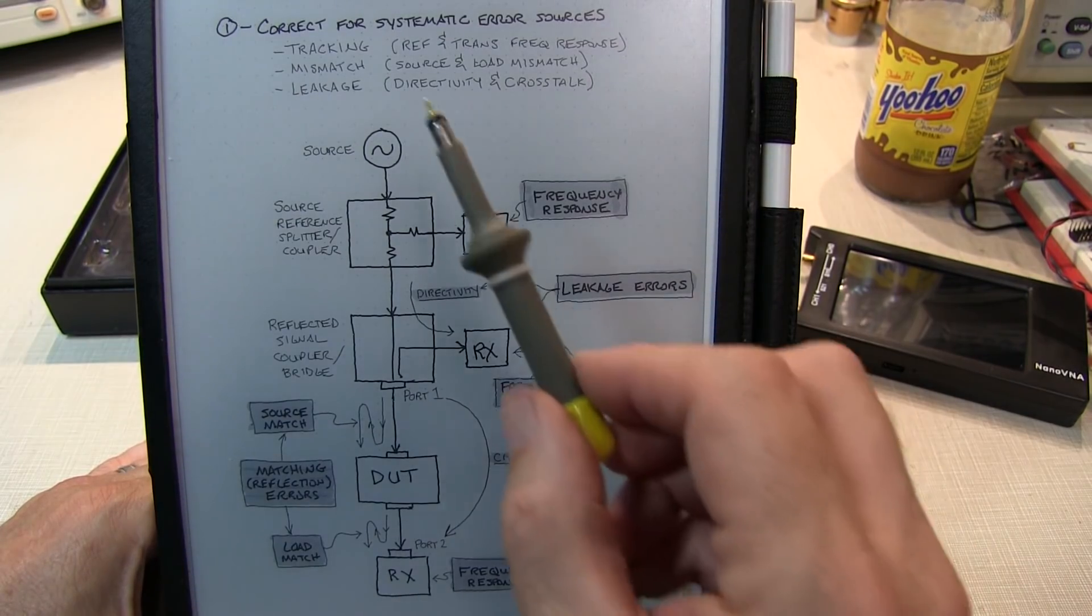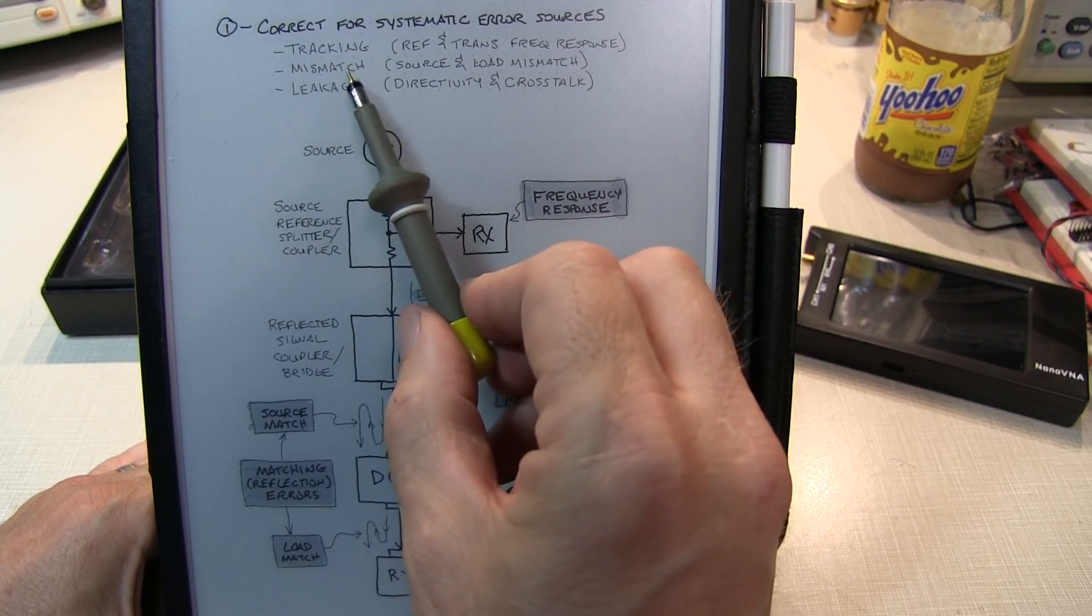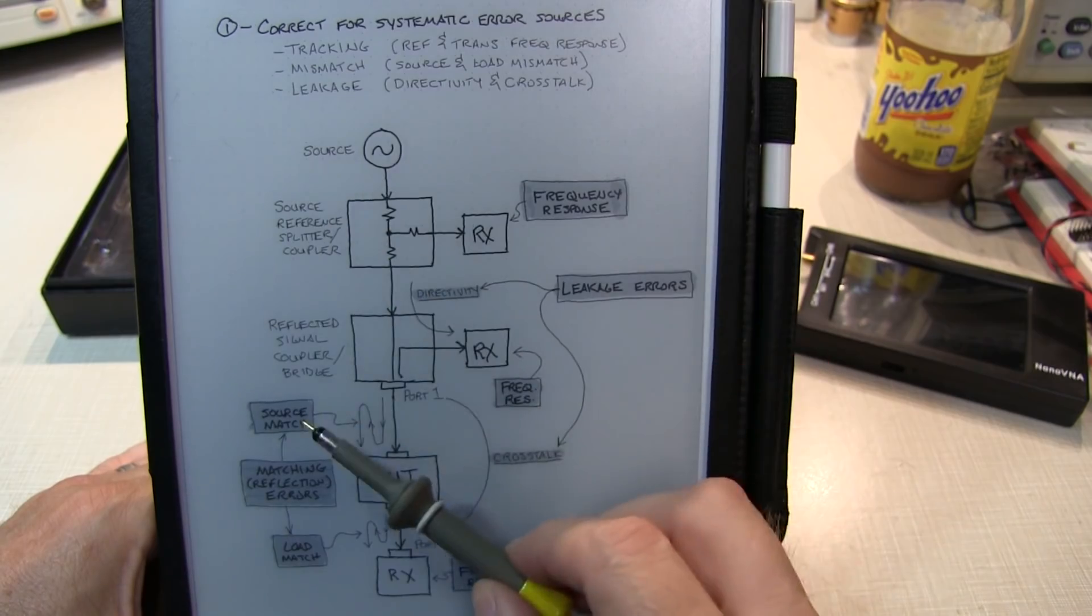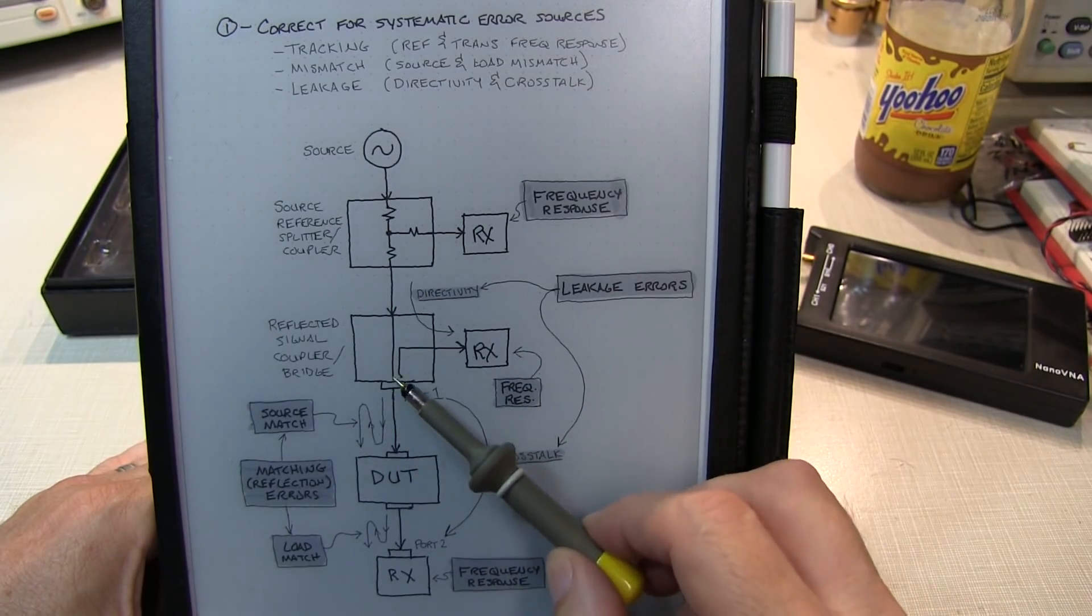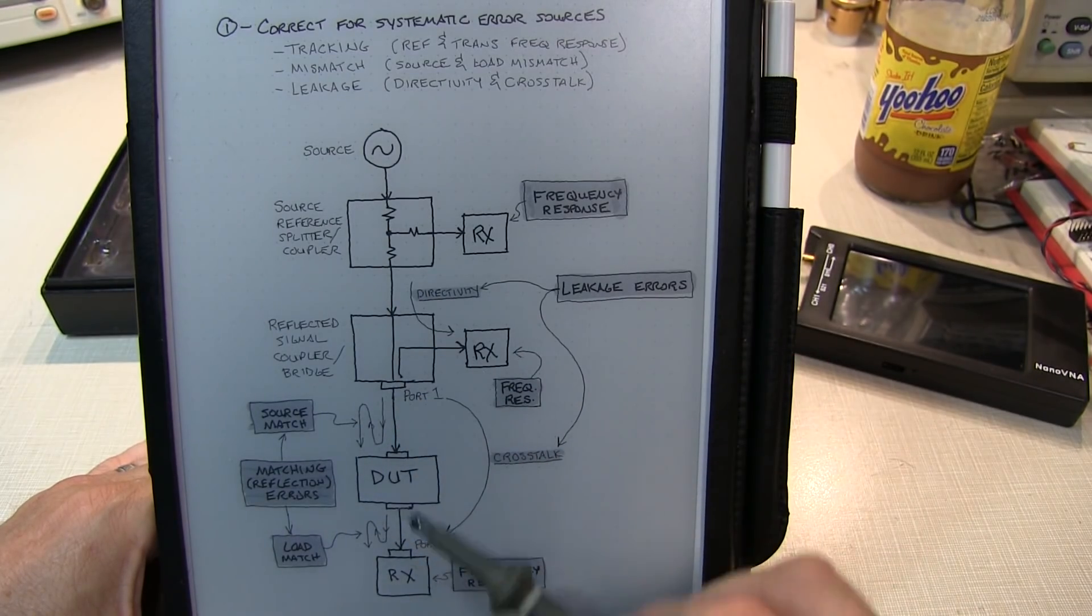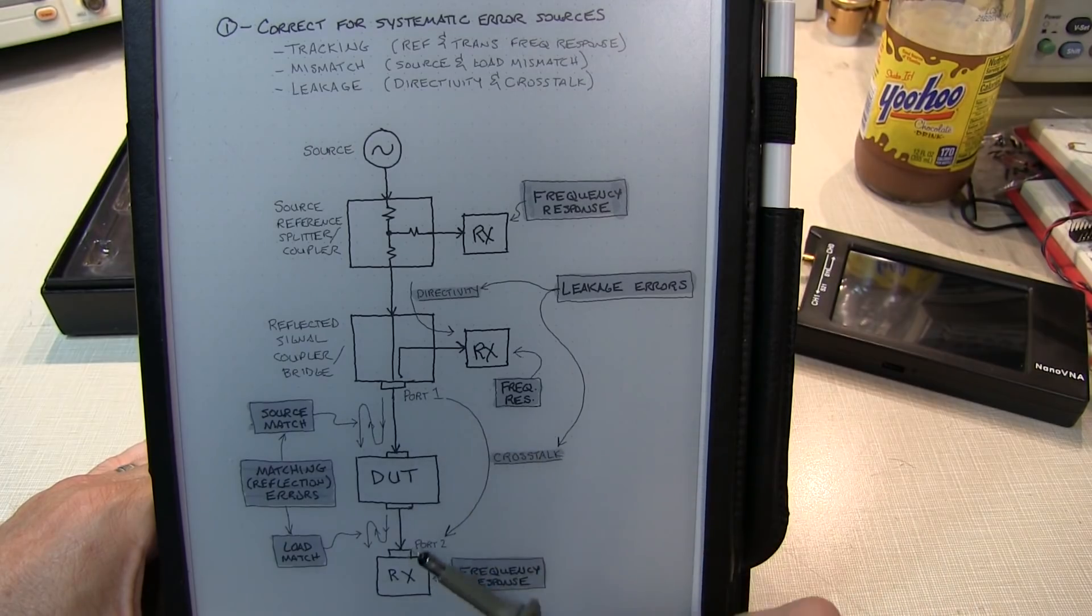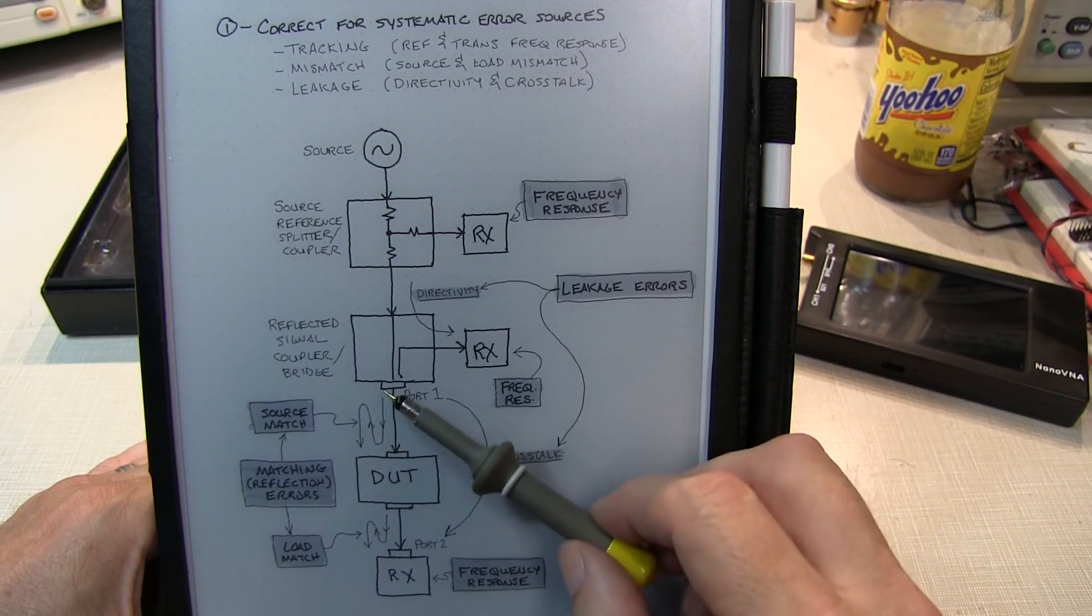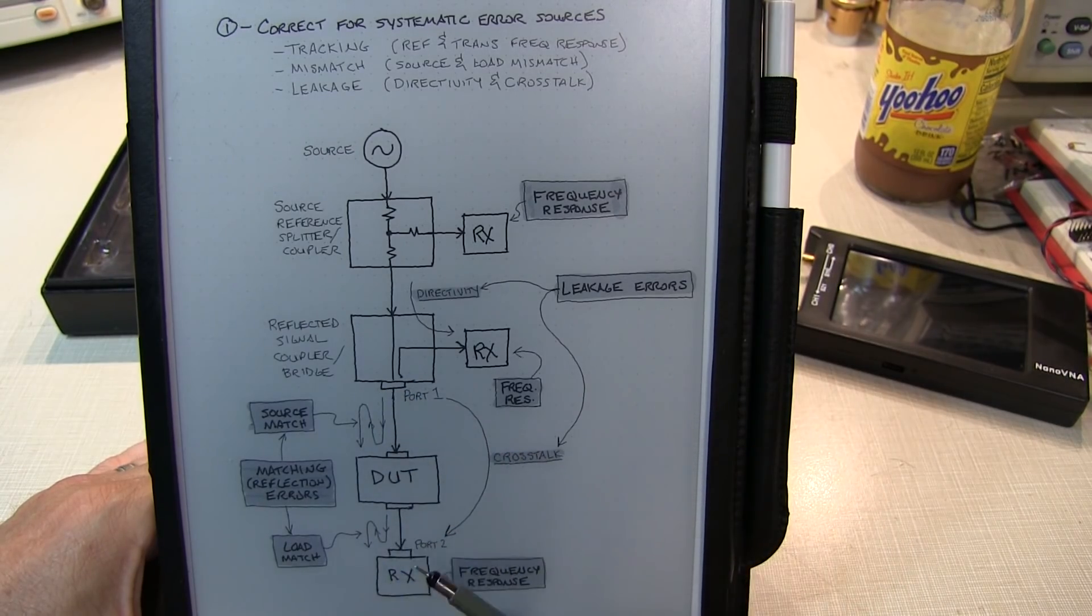Now the next class of errors to correct for are mismatch errors or matching errors called the source match and load match. And that has to do with the impedance matching at the ports of the VNA that will cause reflected energy to then bounce back towards the DUT and vice versa. So we need to correct for those as well.